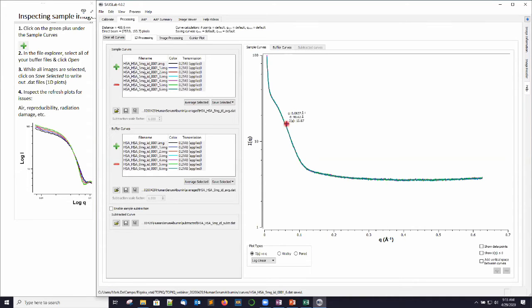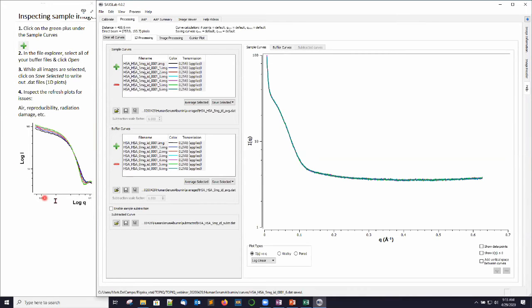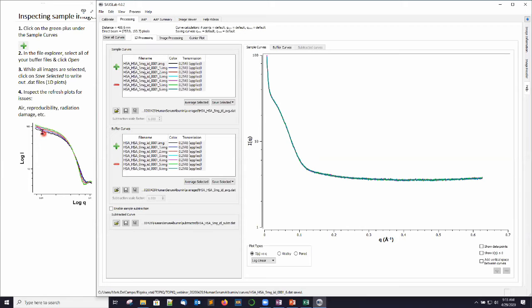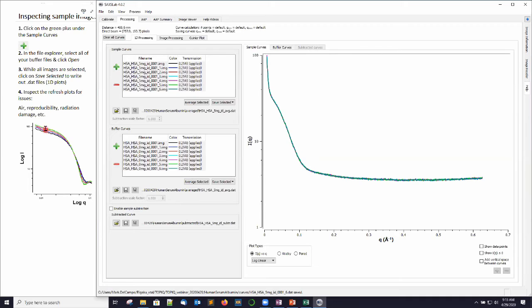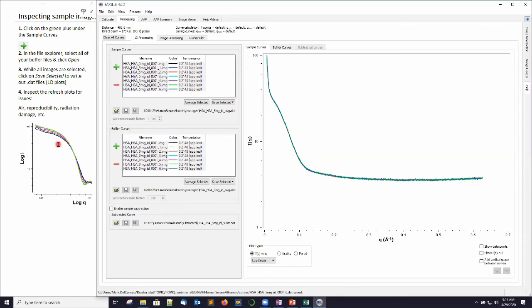In addition to issues of seeing air with the sample, you're also interested in seeing whether you have radiation induced damage to the protein sample. So I don't have any in the HSA, but on the left side, I'm showing you a picture of what you would see. So this is a log-log plot of the intensity versus Q. And you can see in this set of curves, starting with the black curve, which is the first interval of time, each subsequent image, the intensity is increasing. So this systematic change of increasing intensity with subsequent exposures is a telltale sign that you are getting radiation induced damage, radiation induced aggregation, or structural changes due to x-ray. So that's something you want to take a look at.